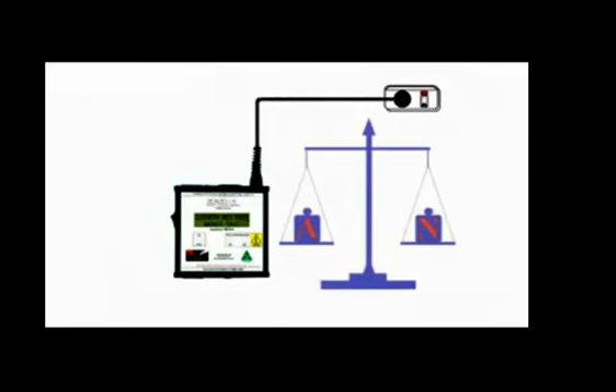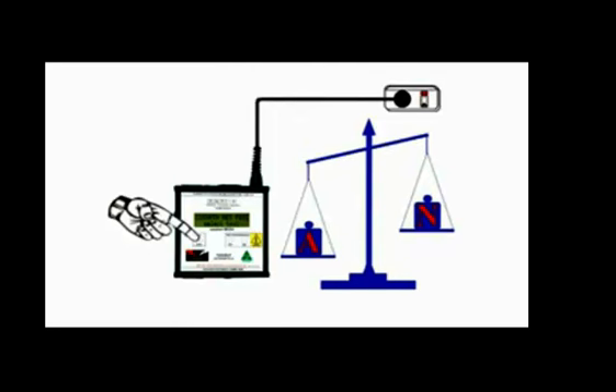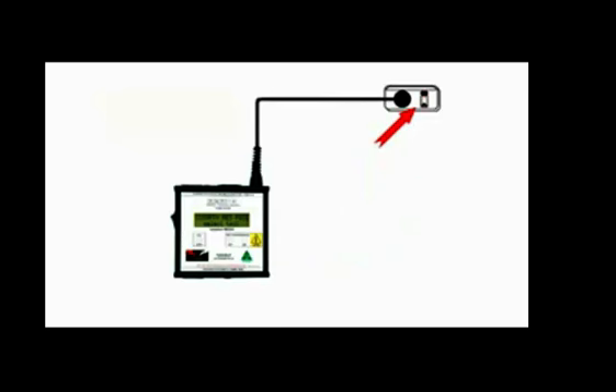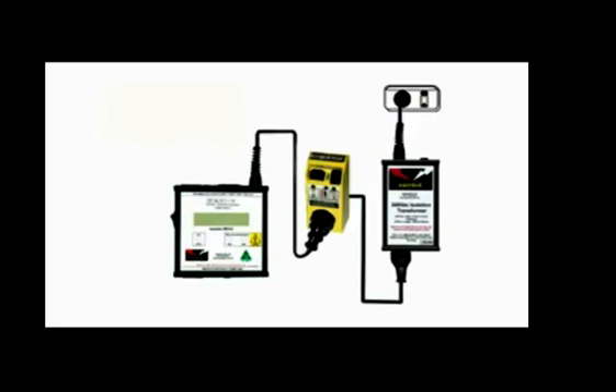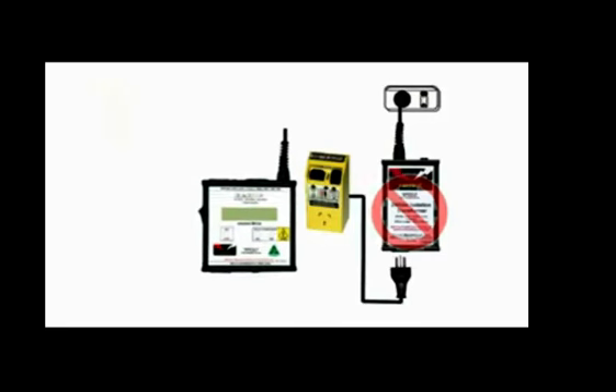Appliances that are working correctly present a balanced load to the mains. That is, the current on the active and the neutral are the same. The job of the EASYTEST Mega, in RCD mode, is to pretend to be a faulty appliance and provide an unbalanced load, which of course will trip out any RCD protection on the building's main switchboard. To prevent this, most RCD testers would need an isolation transformer, but the Mega has a better way.